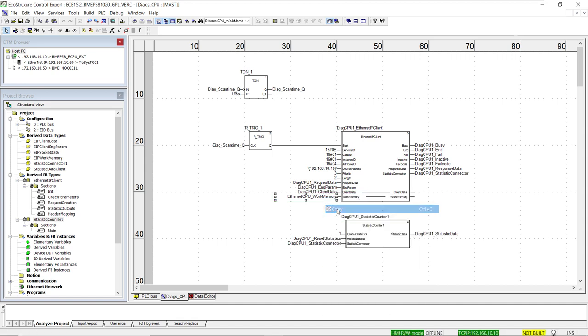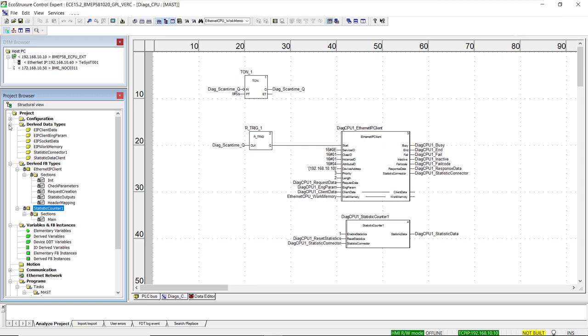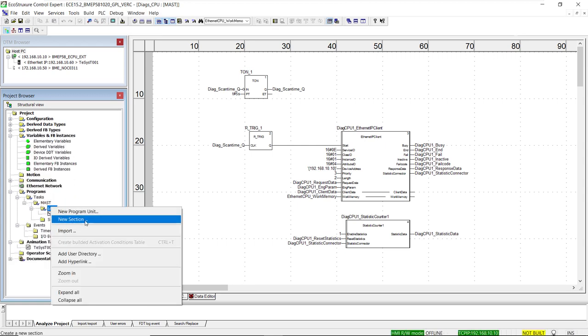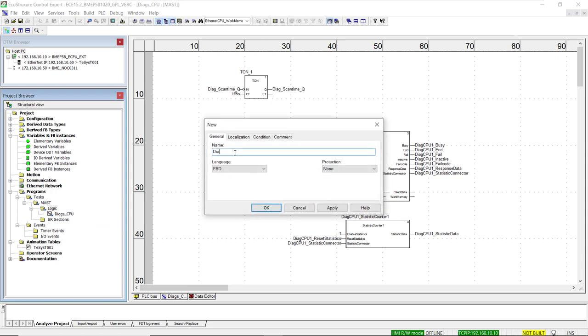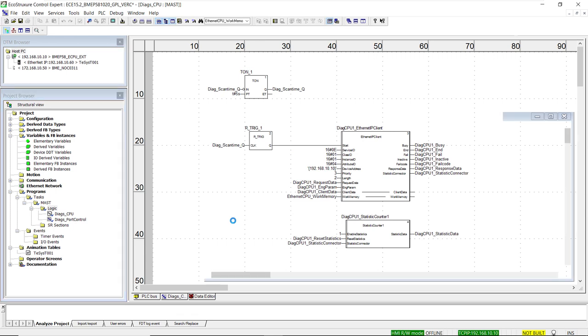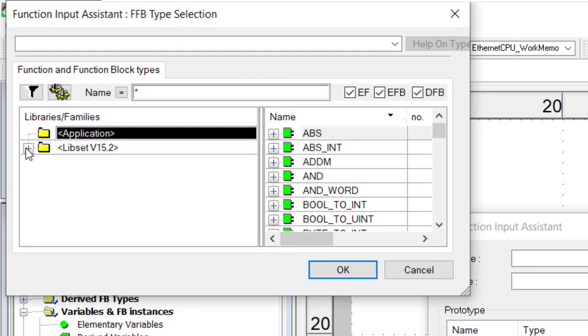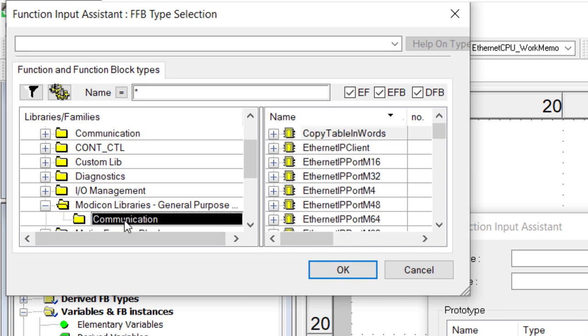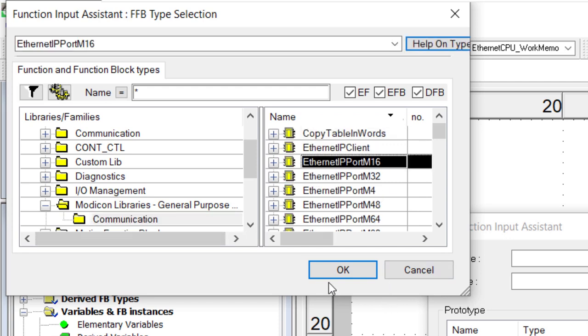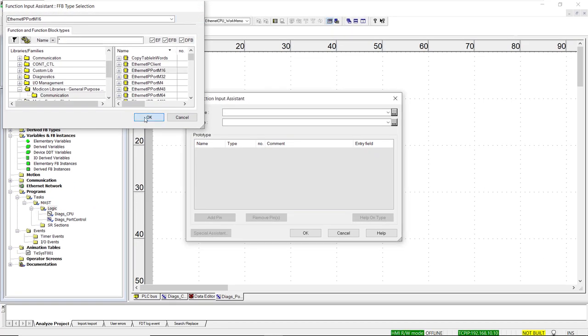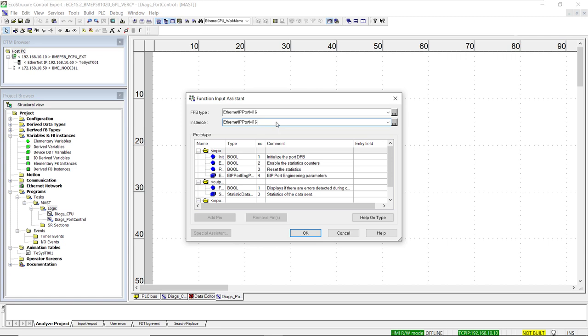Once we copy that variable name, we create a new section placed after all Ethernet IP client function blocks linked to that port profile function block. We find the port profile function block using the function block input assistant, navigate to the general purpose library folder, then the communications folder. Several options are available; the number at the end distinguishes the different port profile function blocks. We select the one ending in 16, matching the capacity of the CPU we are working with.